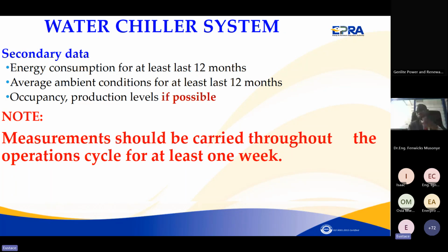Also look at power consumption, energy consumption, occupancy levels or production levels if it's a factory, and even if it's a data center, you can establish the consumption of the IT machines. Measurements should be carried out throughout the operation cycle for at least one week in a cooling system. It's good you do it for that.